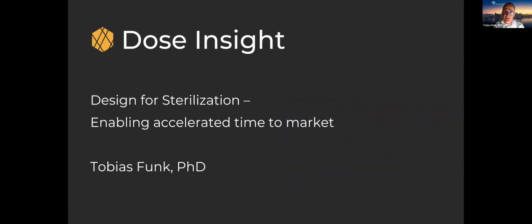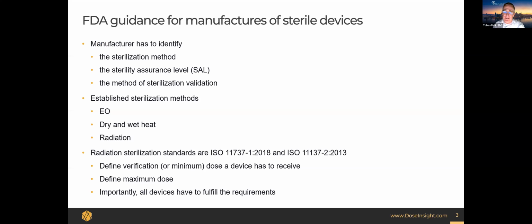Today, I want to focus on design for sterilization and how virtual dose mapping can enable an accelerated time to market for your products. As a brief overview of FDA guidance for manufacturers of sterile devices, by no means will I give a comprehensive overview, but I'll try to give some nuggets that are important. For guidance, the manufacturer has to identify the sterilization method that is going to be used, the sterilization assurance level, basically the likelihood that something fails, and then the method of sterilization validation.